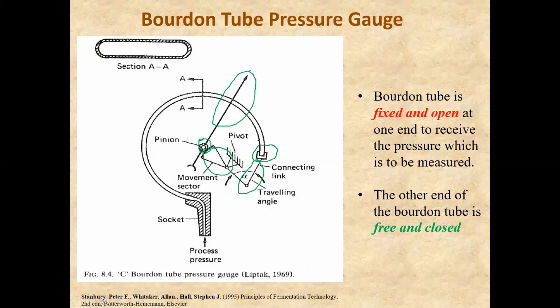So what is the working of this Bourdon tube pressure gauge? I've told you the principle, I've told you the construction. What is the working, or how does it work? Now the pressure to be measured is connected to the fixed open end of the tube, which is this one. The applied pressure acts on the inner wall of this Bourdon tube, and due to the applied pressure, the Bourdon tube changes in cross section from elliptical to circular, and this tends to straighten the Bourdon tube, and this causes a displacement of the free end of the Bourdon tube, which is this one. So because of the pressure of the liquid, this is a pressure gauge, this is monitoring the pressure of that liquid or gas.